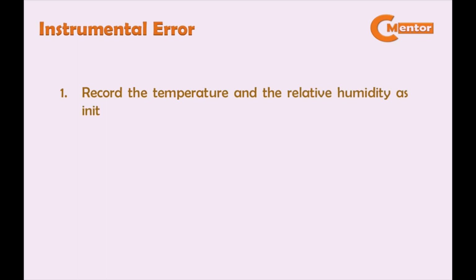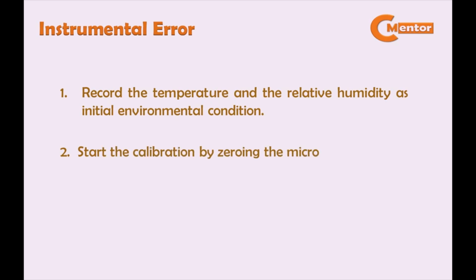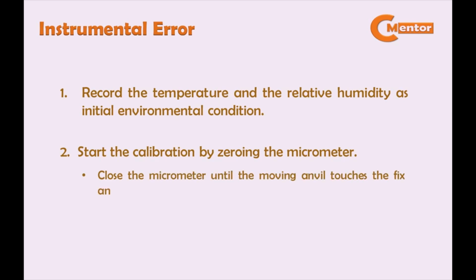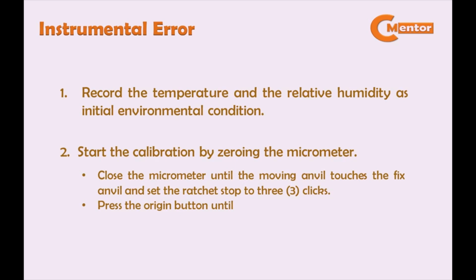This is the procedure on how to determine the instrumental error of the micrometer. First, record the temperature and the relative humidity as initial environmental condition. Second, start the calibration by zeroing the micrometer. Close the micrometer until the moving anvil touches the fixed anvil and set the ratchet stop to 3 clicks. Press the origin button until the INC display disappears.